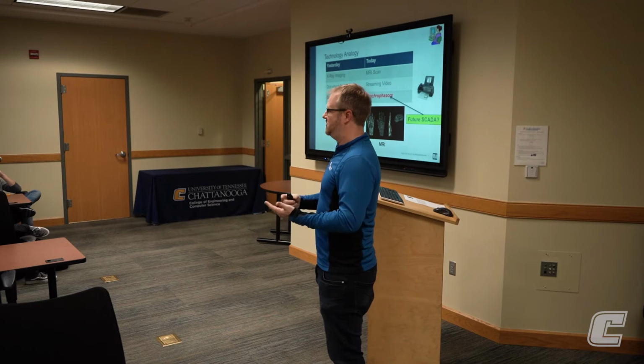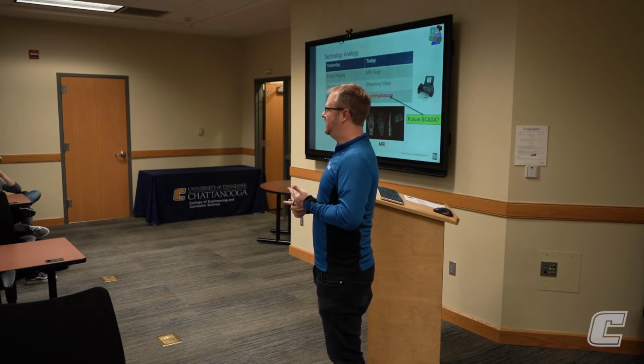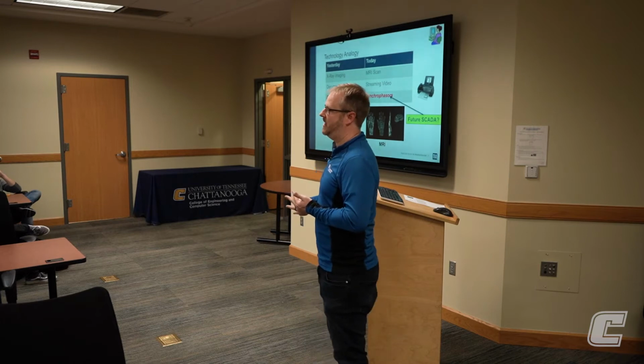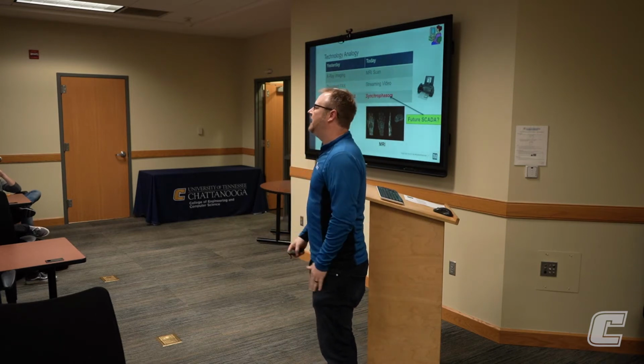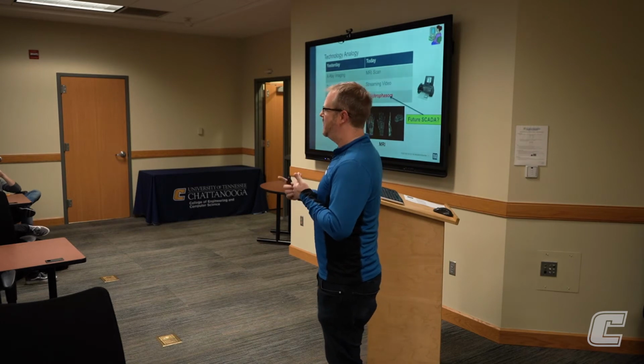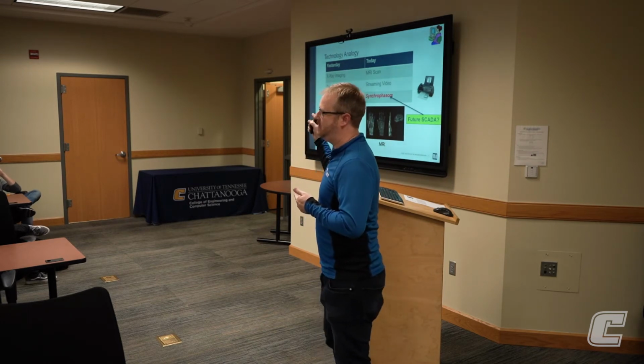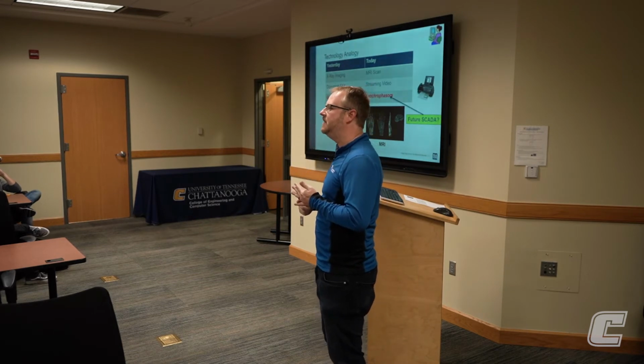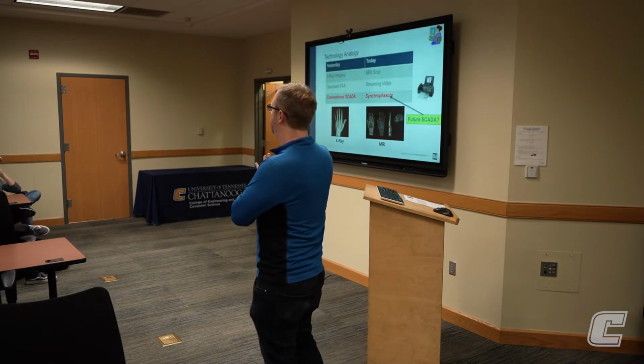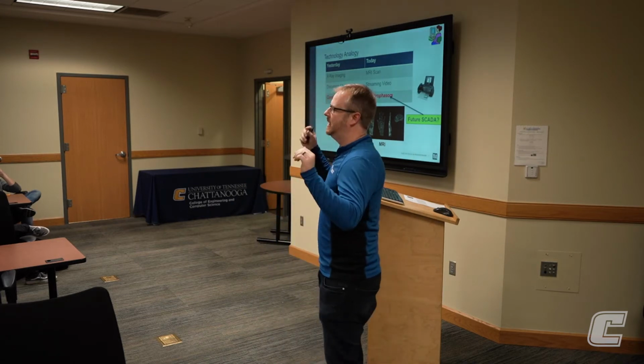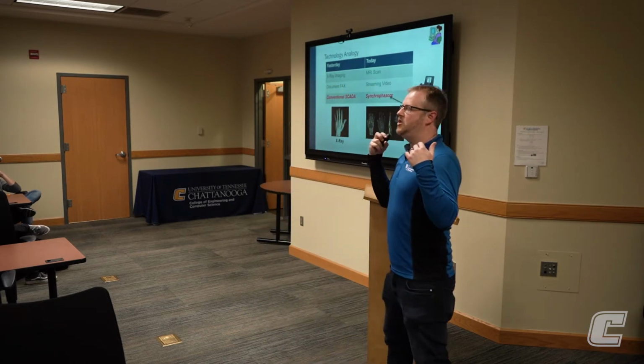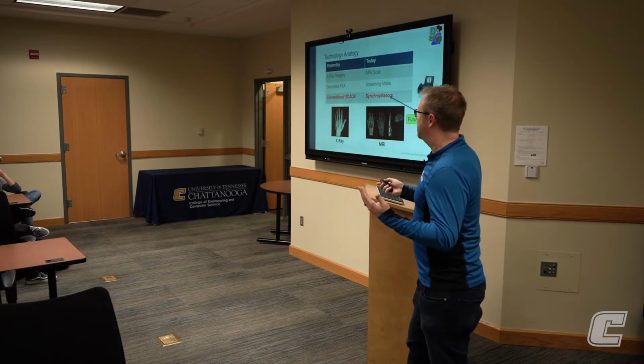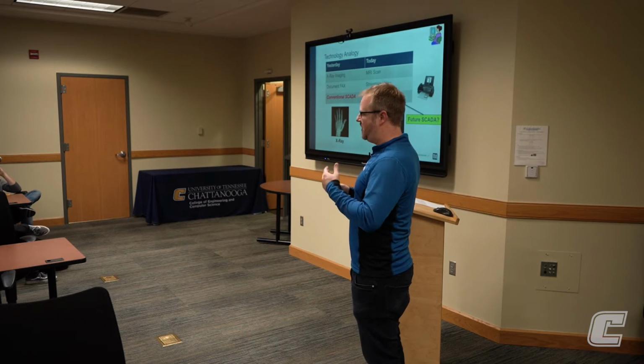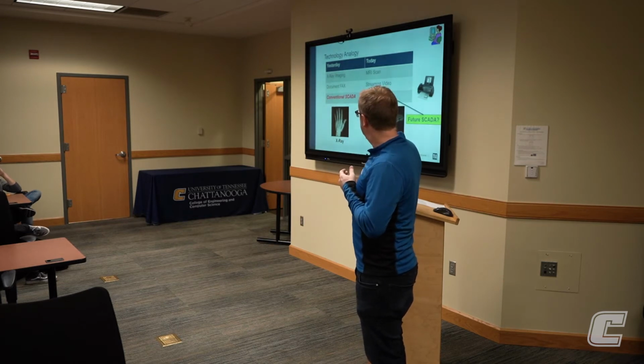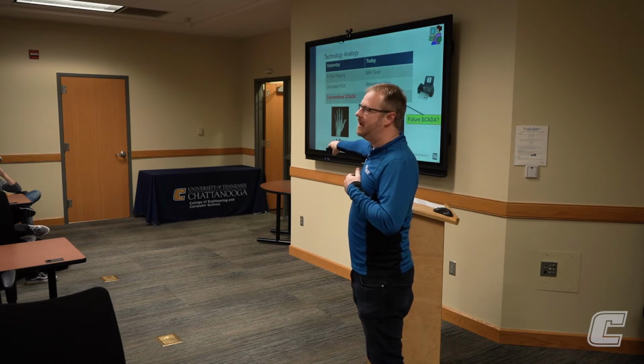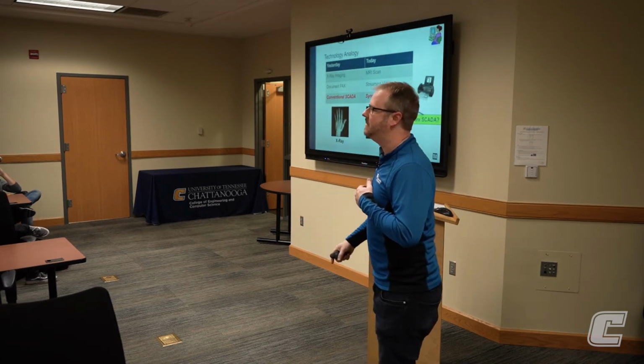SCADA is great, it measures voltage and current, but it's really slow, about a sample every 2 to 5 seconds, and it's not time stamped. So you may be getting something 30 seconds late from Memphis telling you a breaker just opened or closed, or a unit just came on. It's what's been used in the industry for years, and it works, it's just slow and not time stamped. The analogy is it's kind of like an x-ray, it gives you some visibility, but not a ton.